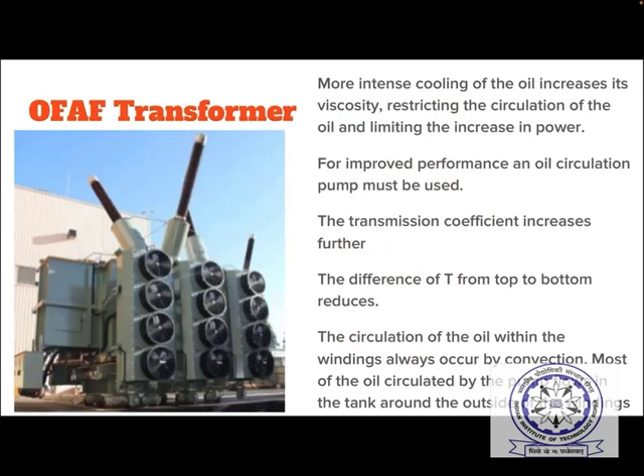Next is OF-AF. Now, in the last transformer, fans were added. In this, oil is also being forced. So you can see at the bottom of this transformer there are pumps which will cause circulation of the oil. More intense cooling of the oil increases its viscosity. Suppose last time we have seen using fans. If we go on reducing the temperature of the cooler, then what will happen?